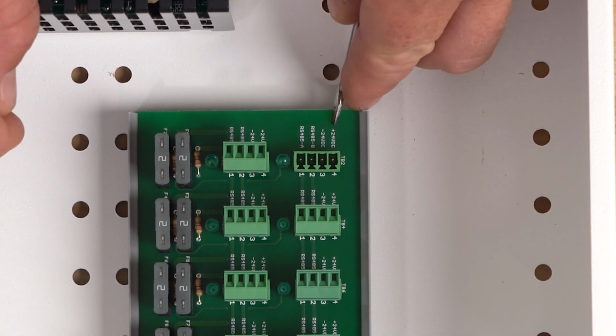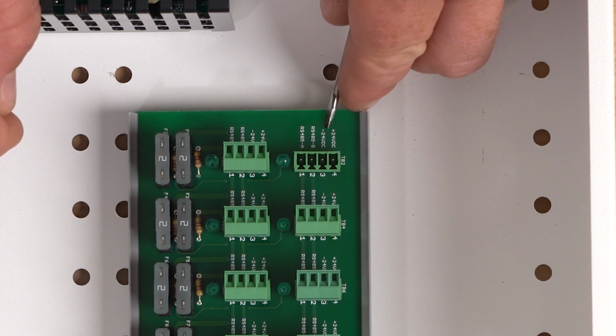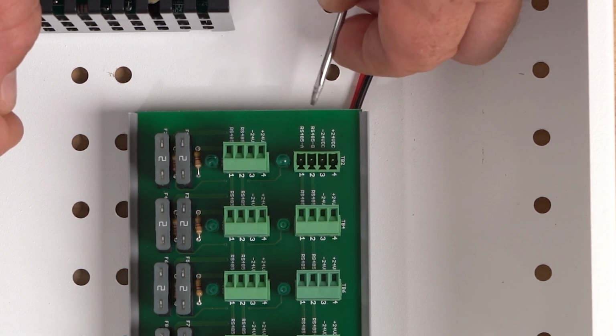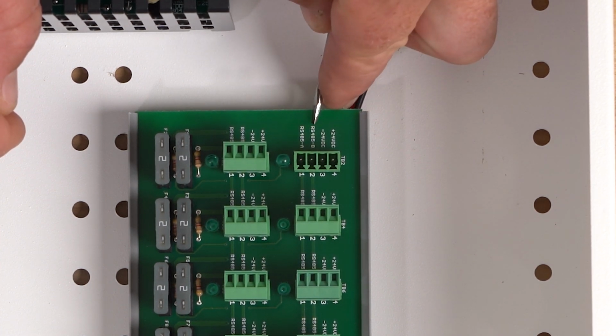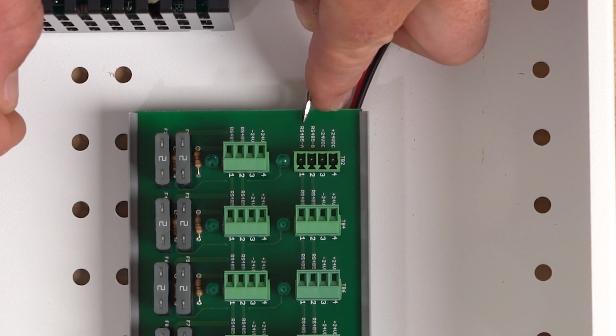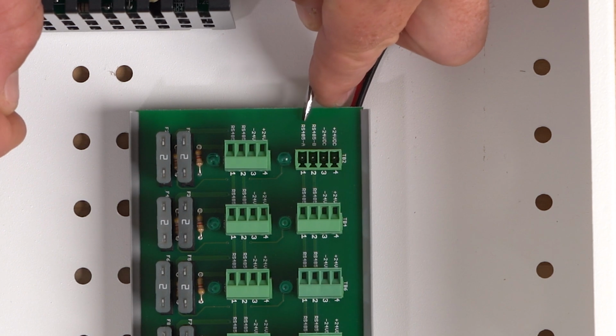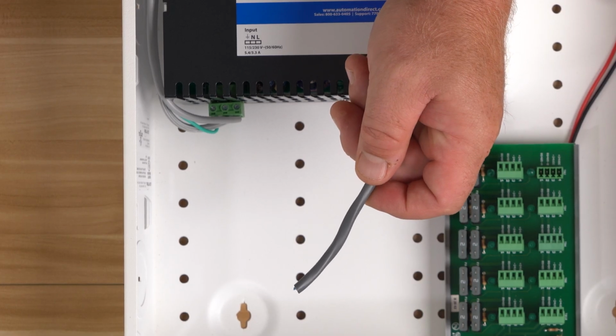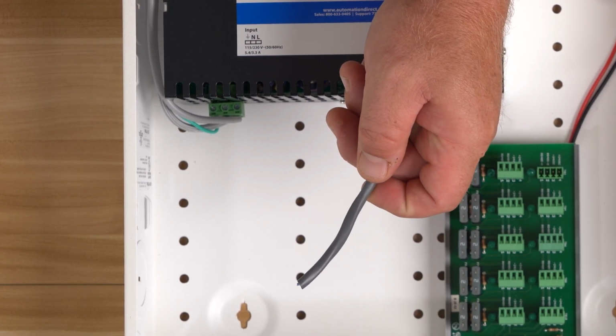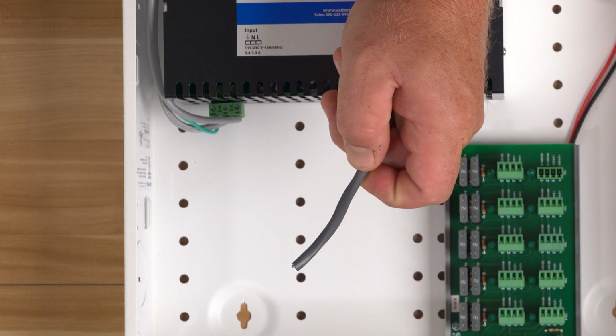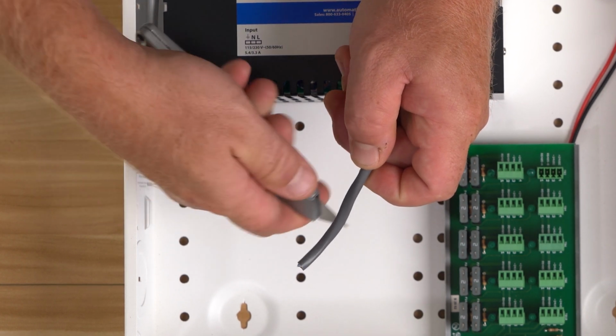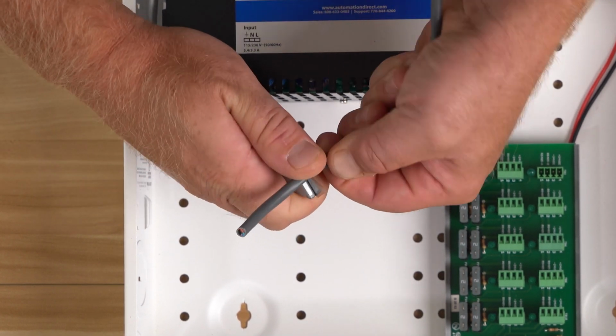For positive, we want to use the red wire. For negative, we want to use the black wire. If you are configuring a 485 system, RS-485B will be the blue wire and RS-485A will be whatever's left, typically a white wire. When making up a wire at the panel, I like to have the wire already made up at the motor, just so when I go to make it up, I don't have to worry about anything shocking or shorting out.